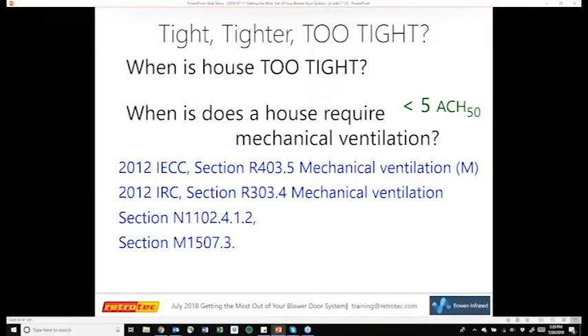Moisture can't get out, and so usually at 5 ACH 50, that's when we want to bring in some outdoor air from mechanical ventilation. And that's going to be from a device such as an ERV or an HRV, or positively pressurized ventilation, such as an air cycler fan, something such as that.